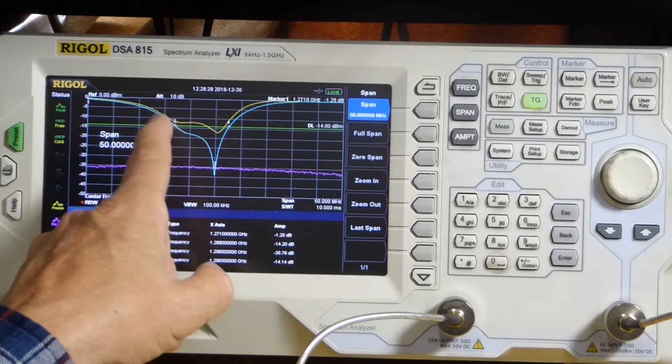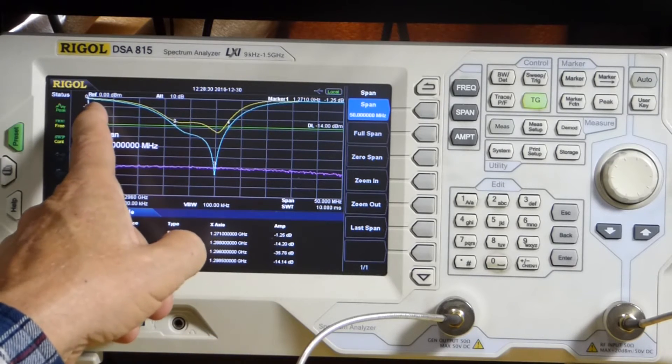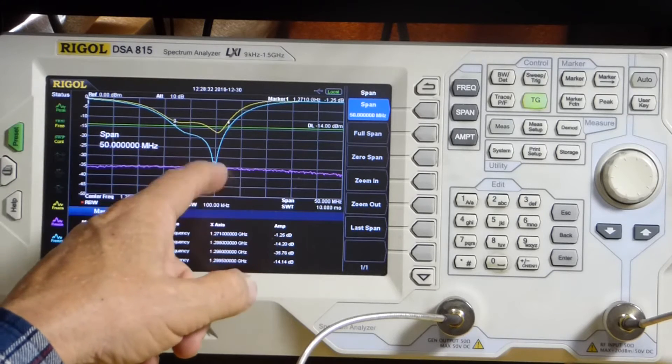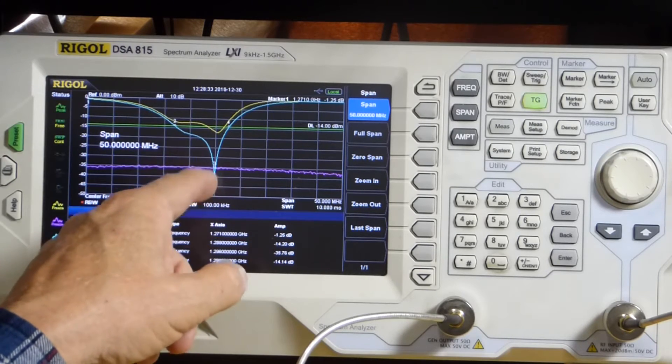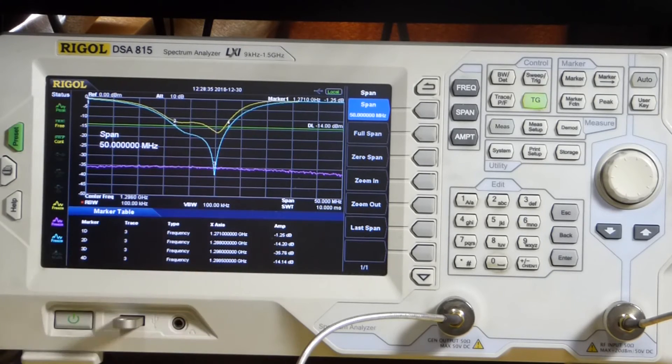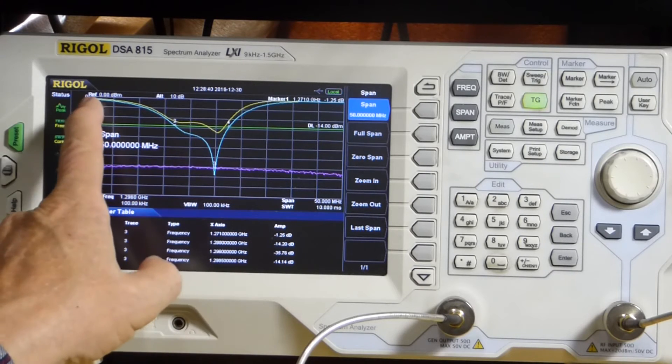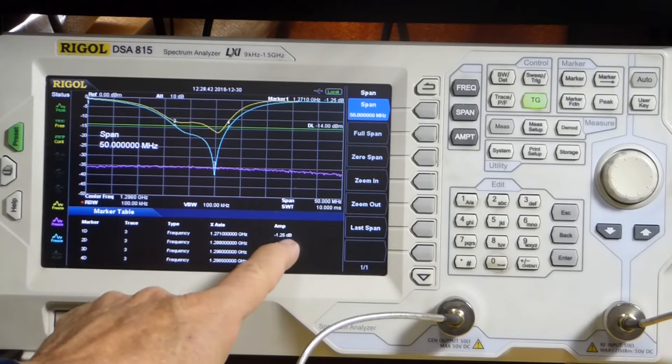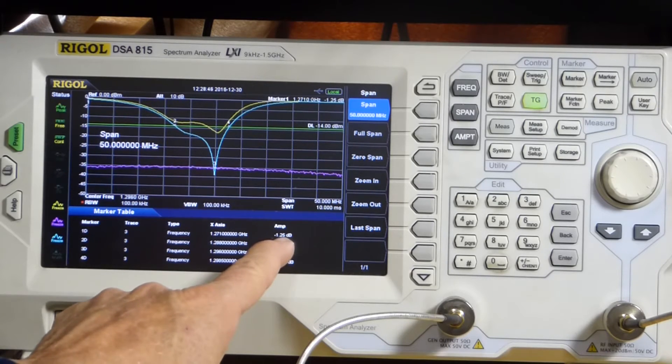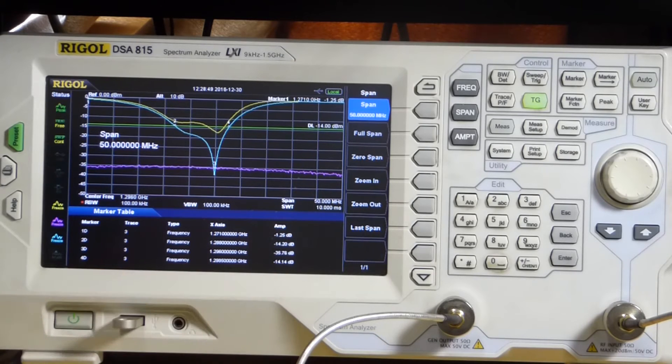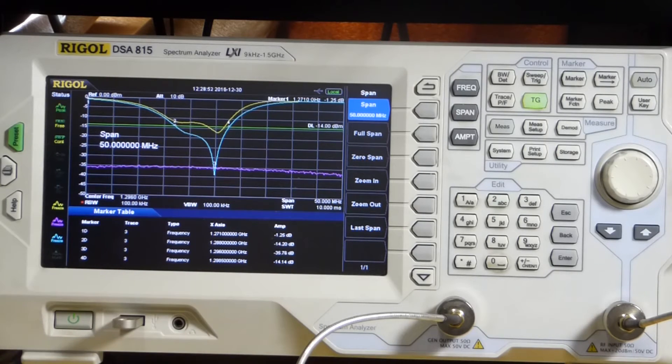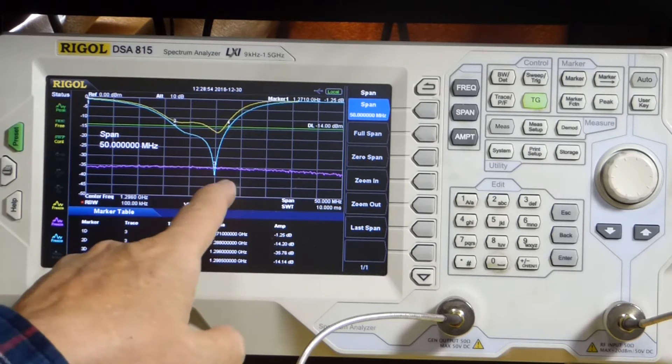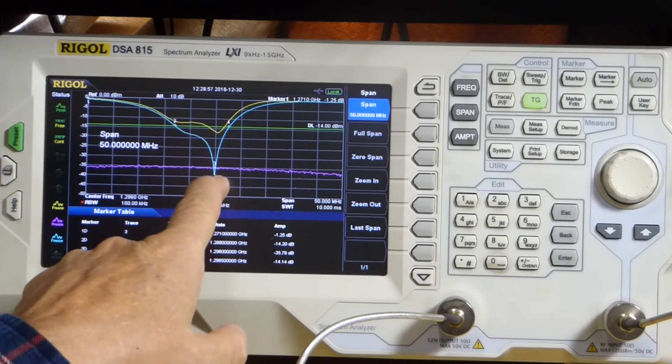And you'll see one of the markers went off frequency, off the edge here. But you still have the markers there. And this is now saying 1271, because that's the edge of the screen now. So it's measuring it correctly. It's at minus 1.25 dB, but it's not where we set it.